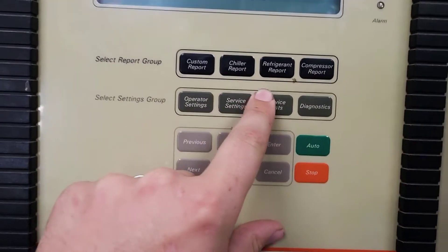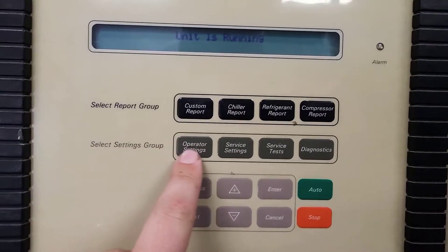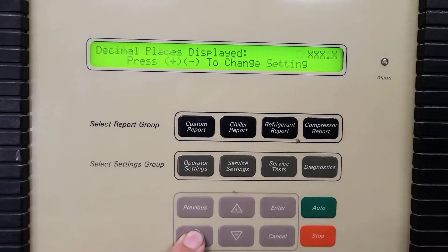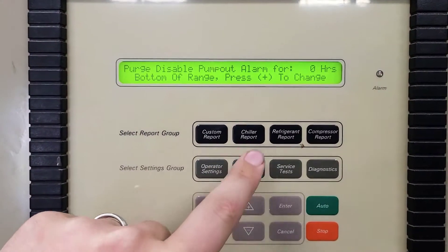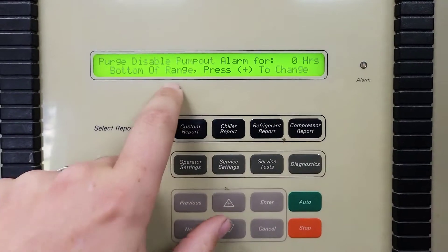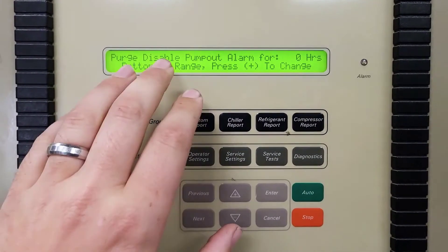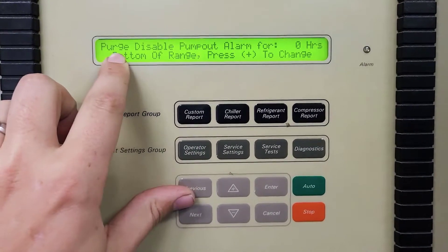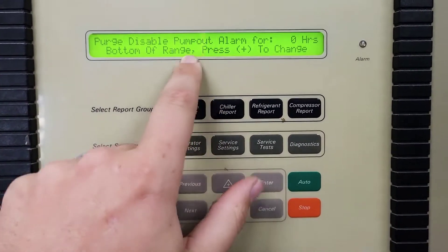If you're at a main control panel — I have the older adaptive control here — where you would do that on this panel is under service settings. You're going to go to service settings, cycle over. It's going to be under the field settings and you're going to have to input the password. You'll cycle through that menu and you'll come to this.